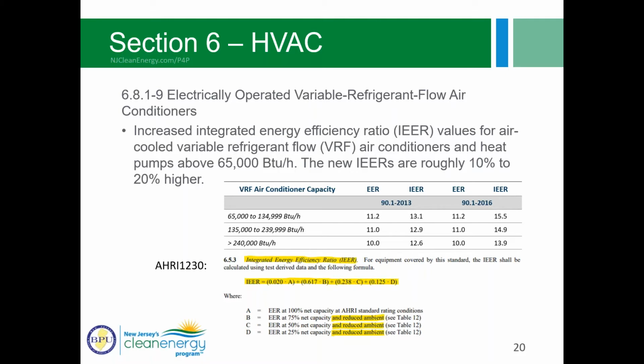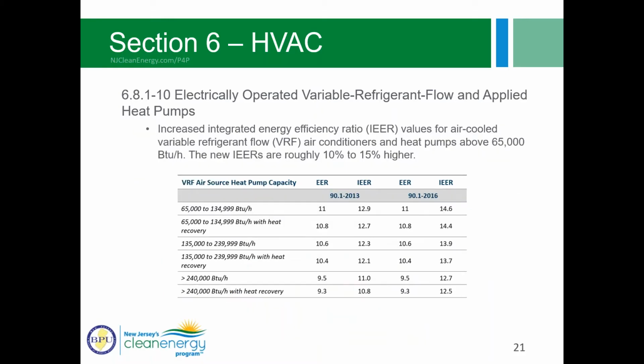I included the AHRI 1230 equations down there for you if you're interested to see how the percentages of those operating bins fit. So those are the changes for VRF air conditioners. Similarly, they did the same for the VRF heat pumps. I didn't include the AHRI values, but it's the same methodology, and you can see here that the EERs stayed the same. The IEER increased slightly, again, to account for a normalized or anticipated operating range.